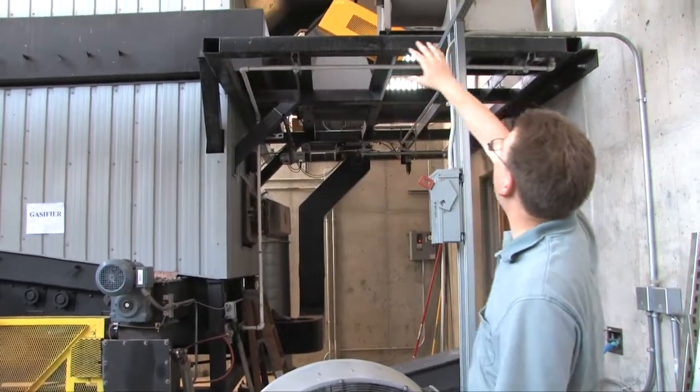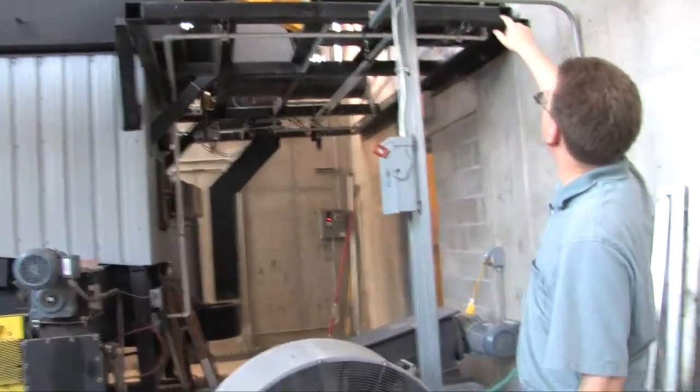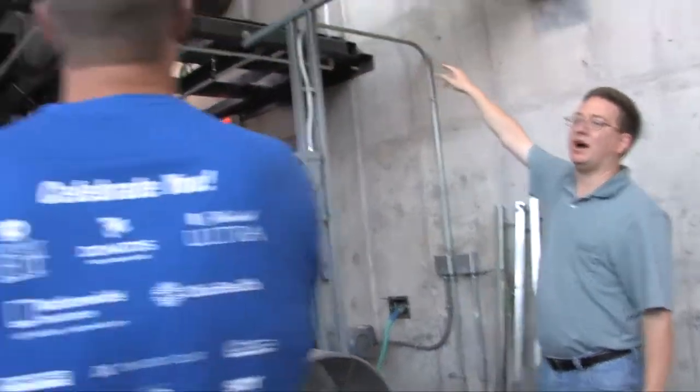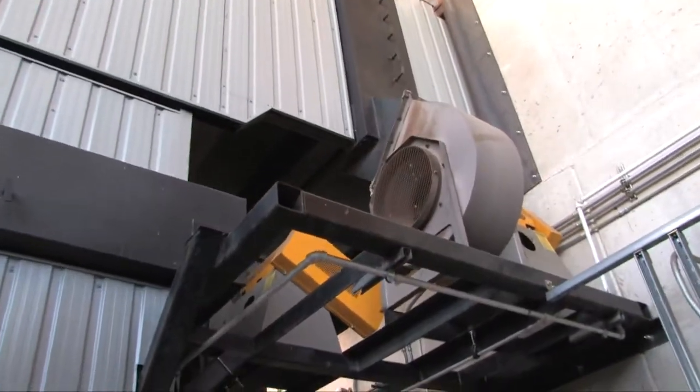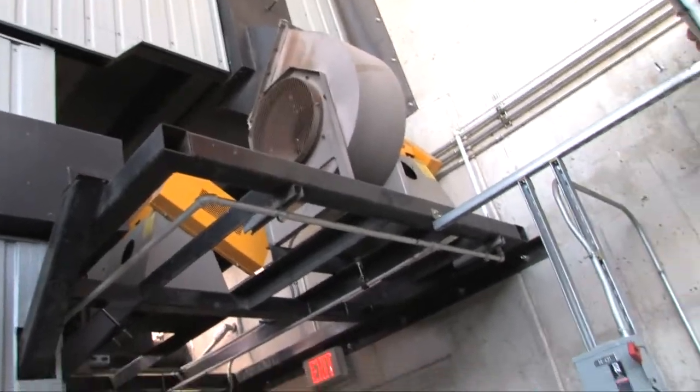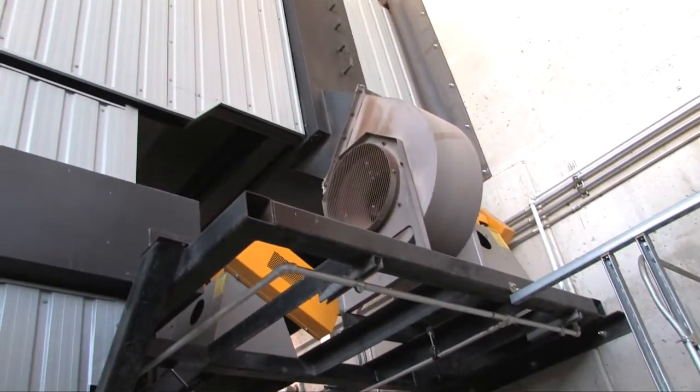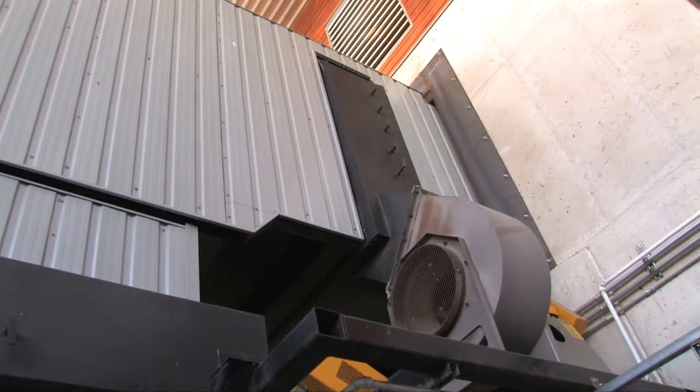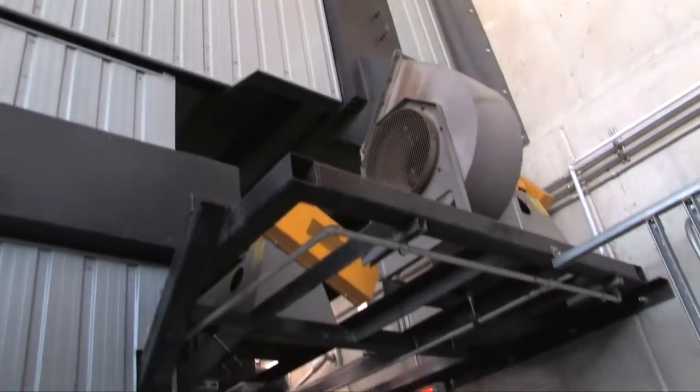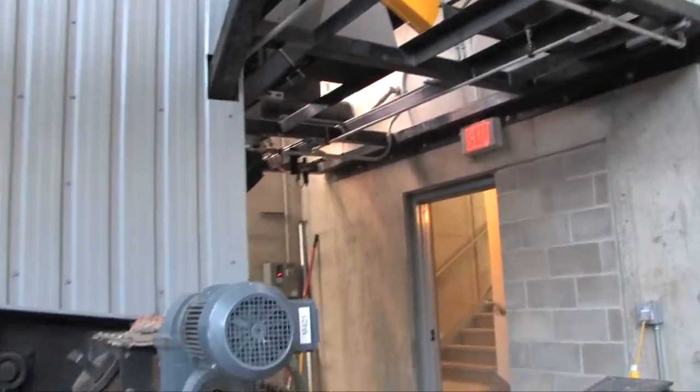And then once we get the gas off it, starting to go up that duct, we have this fan here which will add more oxygen. Once you add the secondary oxygen in there, it starts the combustion process. So they call this a closed-coupled system because right after the gasifier, you start combustion. There are a lot of gasifiers that do have quite a distance between where they use the gas and where they produce it.